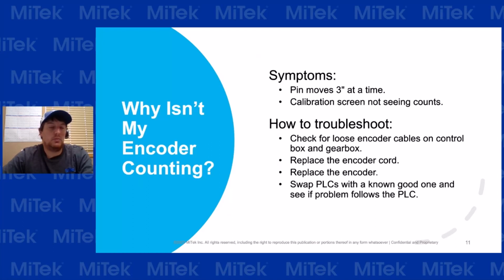Typically, those have big black plastic ends that the encoders and the motors plug into. That is all hardwired into your encoder, so really everything is all in one there. If you see that on your box that you have plastic ends, likely you need to replace the entire encoder and the cable. If you have metal ends and it's a yellow and a gray cord or yellow and a gray end, that is something that screws onto the encoder. The encoder cable screws on the encoder and screws into the control box. You need to check both the encoder and the encoder cable at this point.